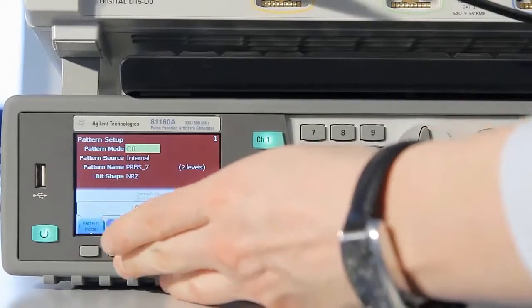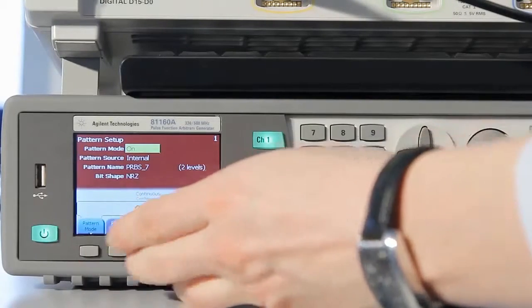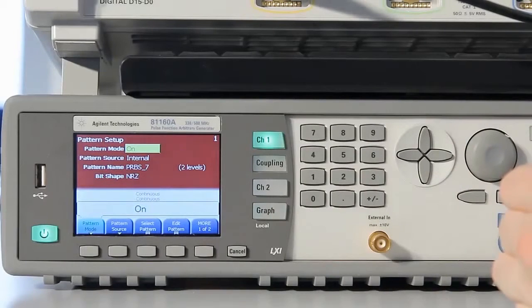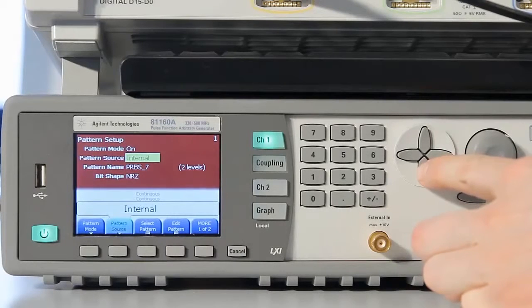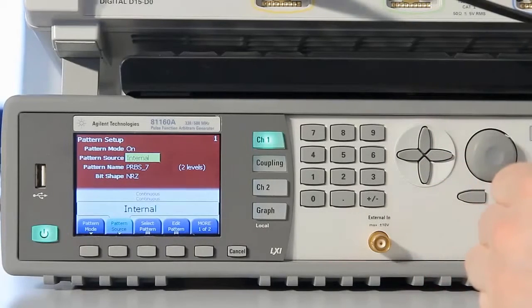Set the pattern setup, pattern mode to on. Leave the pattern source at internal and select the pattern named PRBS_7.